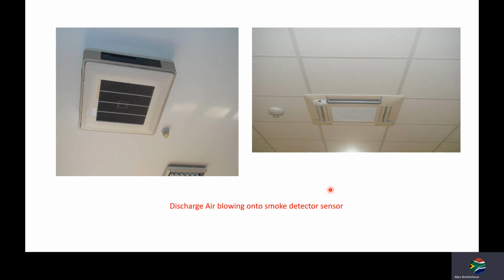Here we can see two cassette units. The discharge air is blowing straight onto smoke detectors. The risk with that is you're going to get a pre-action coming through on your fire alarm system. A lot of nuisance tripping. The Coanda effect is going to throw a lot of dust into those smoke detectors, so avoid any direct airflow into a smoke detector. It's very poor installation practice.